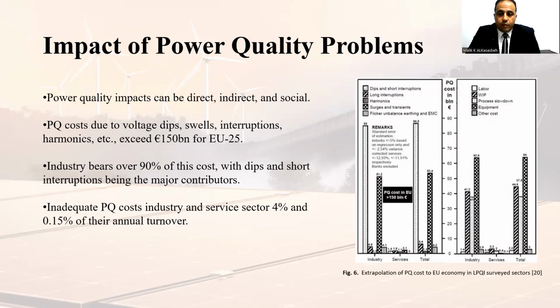Impact of power quality problems: power quality impacts can be direct, indirect, and social. Power quality cost due to voltage dips, short interruptions, and harmonics exceeds 150 billion in the European Union. Industry accounts for over 90% of these costs, with dips and short interruptions being the major contributor. Power quality cost for the industrial and service sectors is between 4% and less than 1% of their annual turnover. We can see in the figure that the costs are more than 150 billion, across the industrial and service sectors and in total.